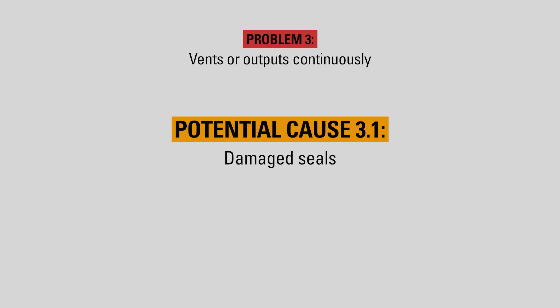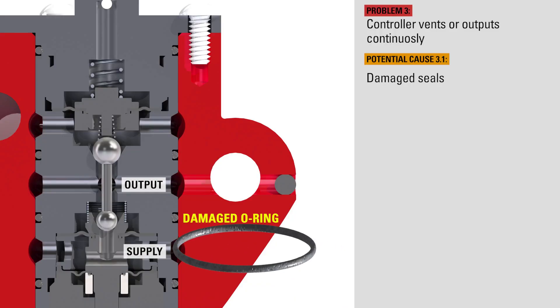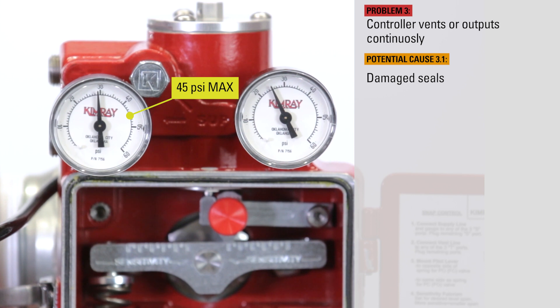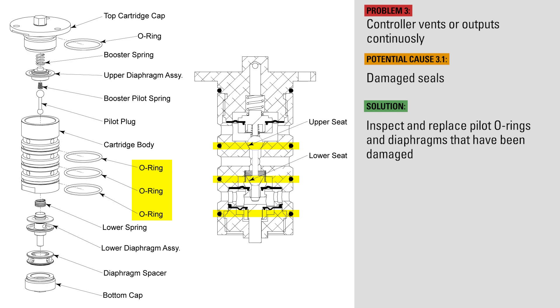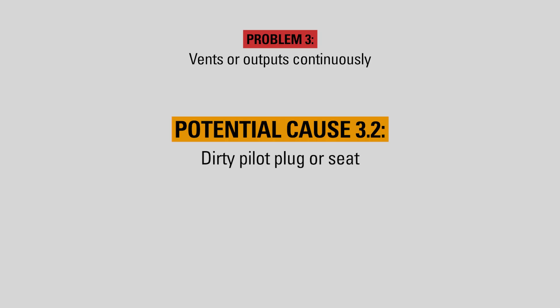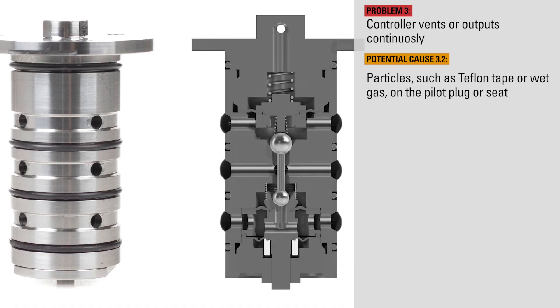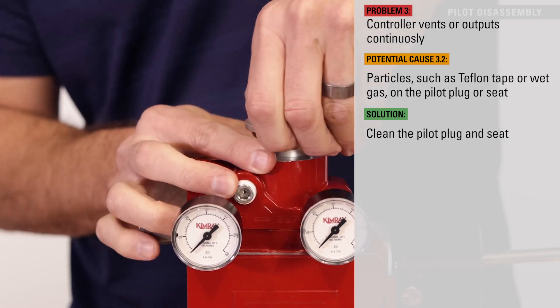If your Gen 3 is sending output or venting continuously, here are the possible causes and solutions. If any o-rings or diaphragms have been damaged, gas could travel to the vent or output when it shouldn't. If the supply pressure has been set to greater than 45 psi, this could rupture the diaphragms in the pilot. Inspect pilot o-rings and diaphragms and replace if necessary. If particles, Teflon tape, wet gas, or any other obstructions have made their way into the pilot, the pilot plug can stick in one position or not fully seat, allowing gas to flow by. Clean the pilot plug and seat and ensure the filter is clean. Instrument gas may need upstream filtration or moisture removal.